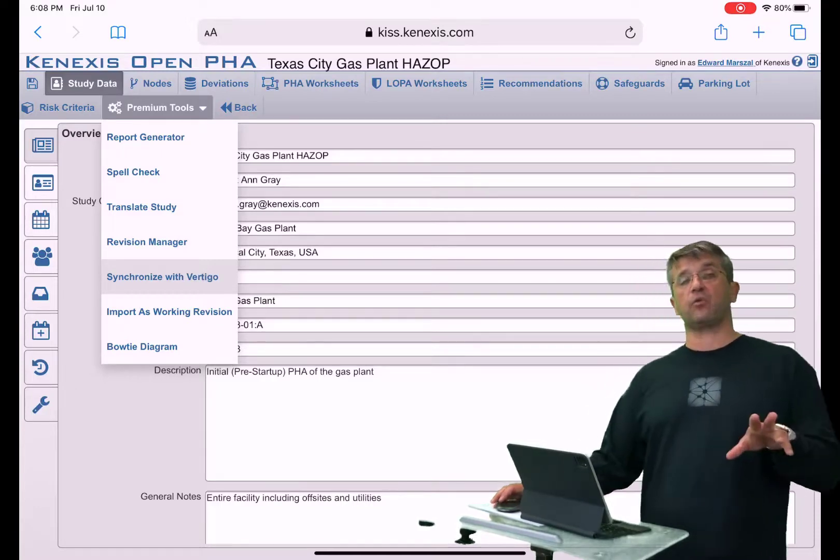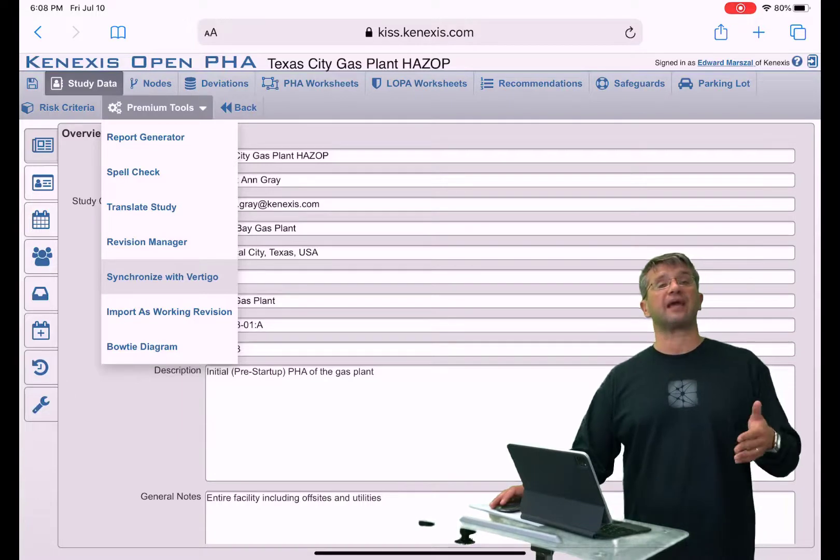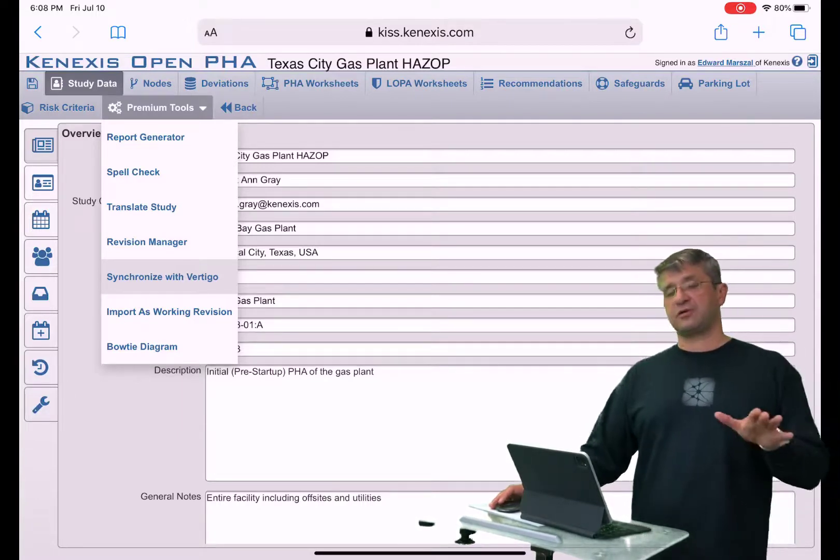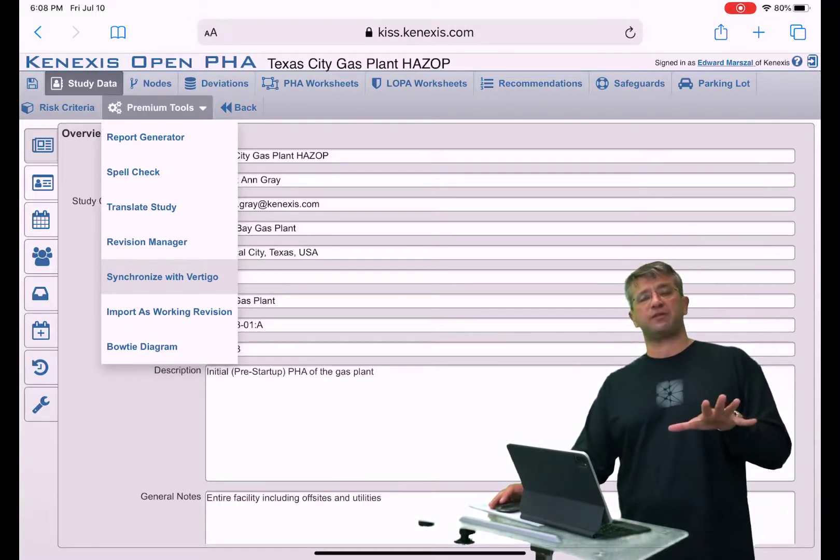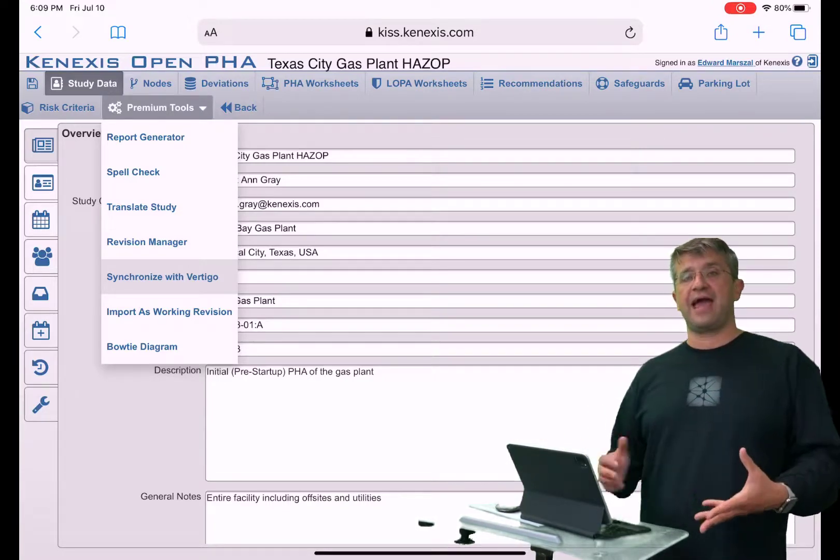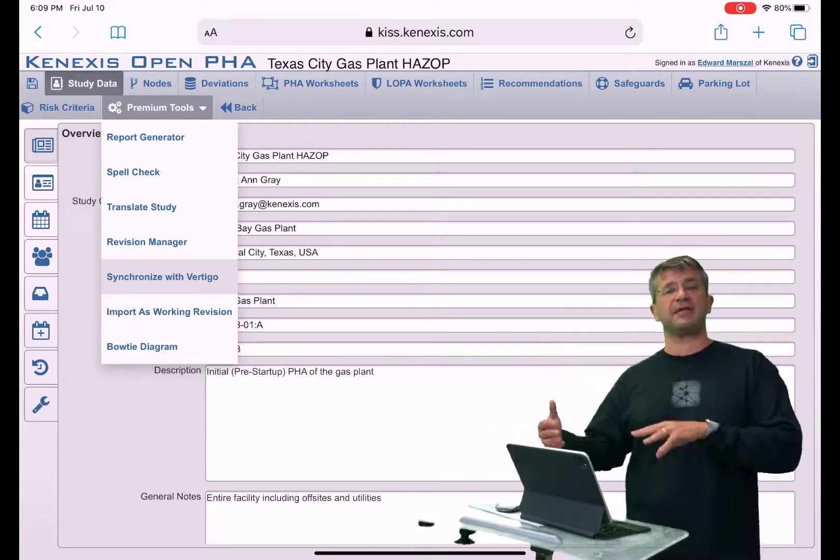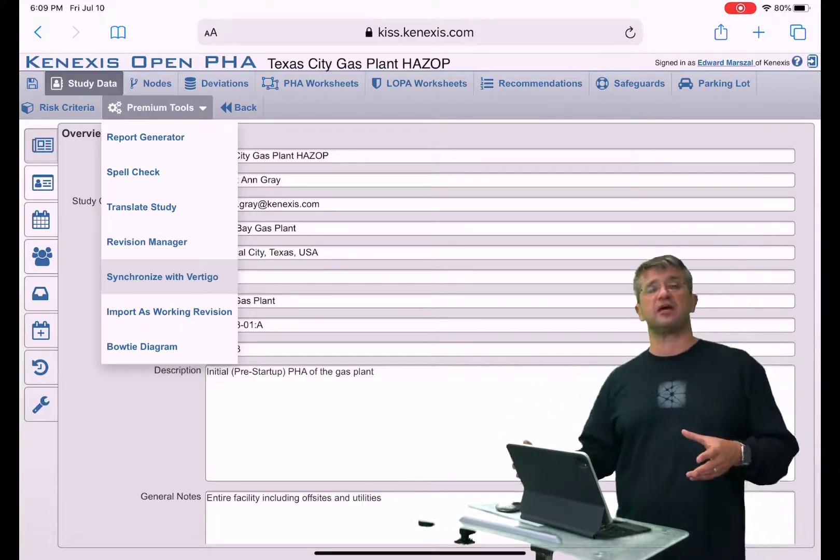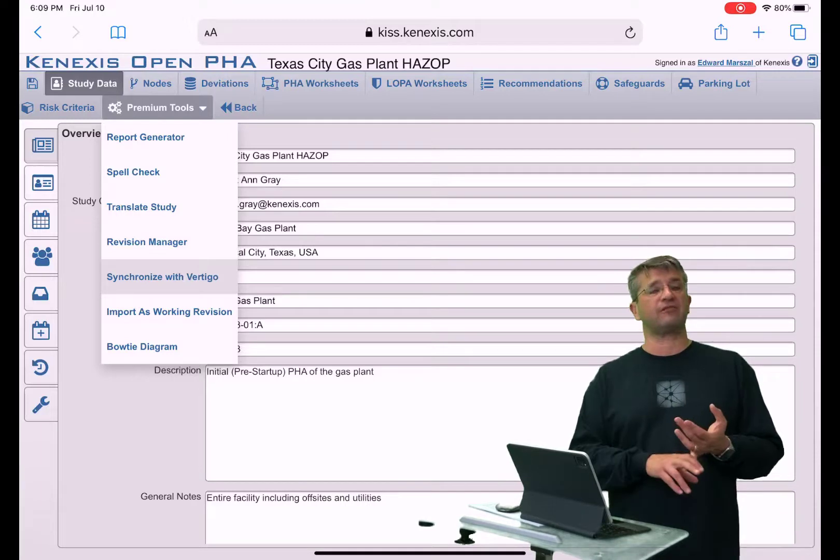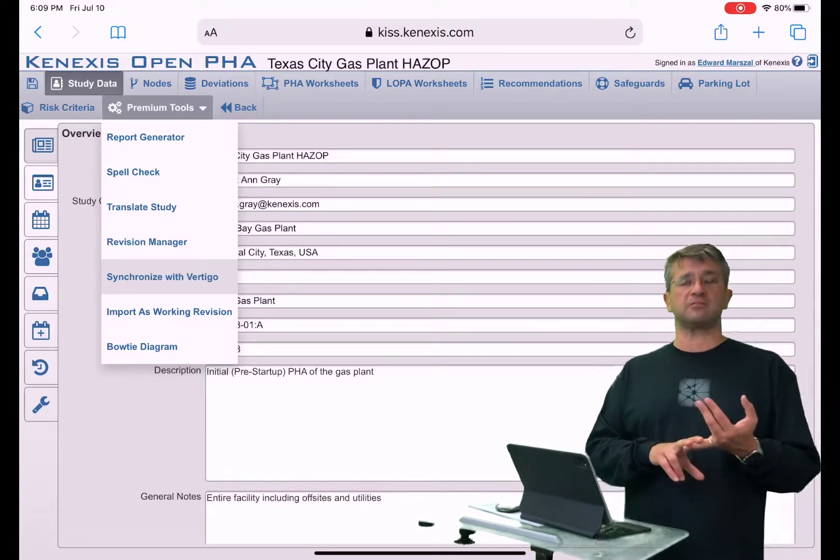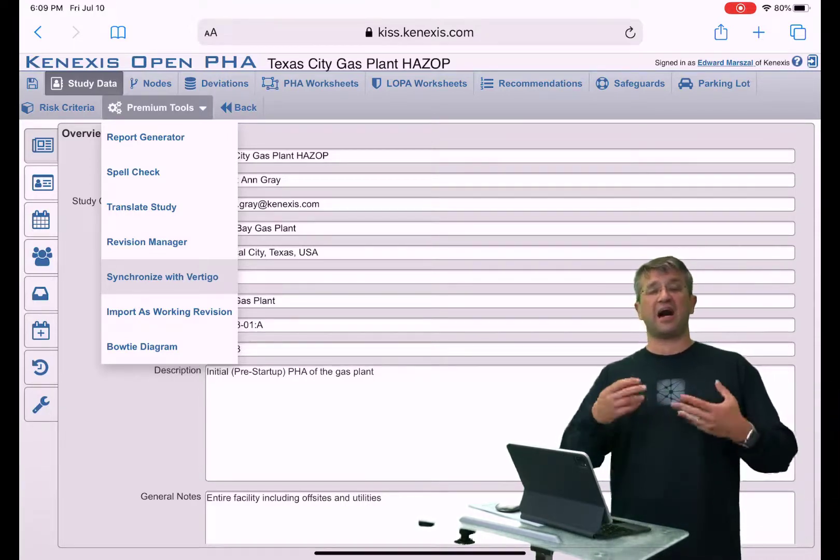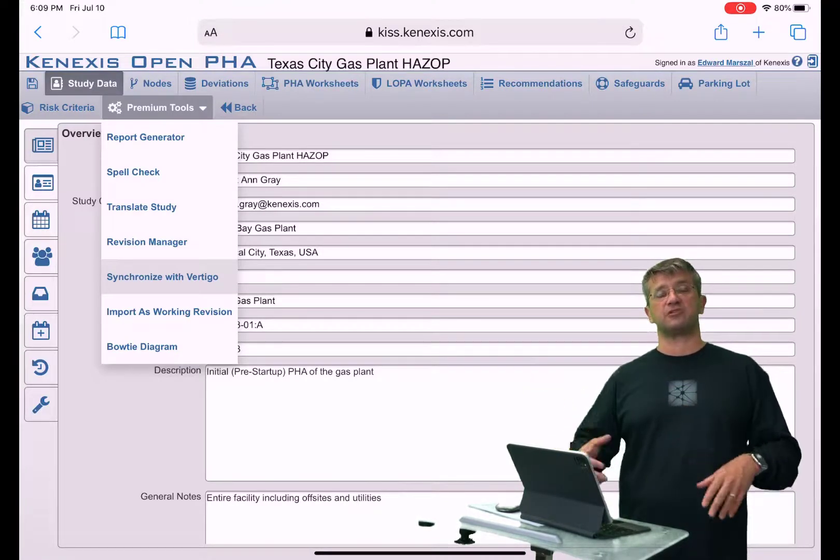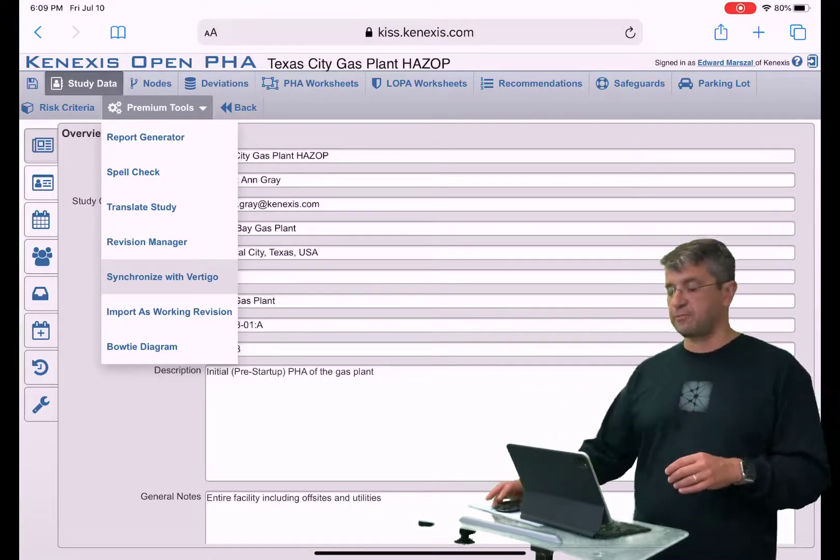Primarily when you're working with Vertigo, you're usually looking at safety instrumented functions. You could take all of the safety instrumented functions that you defined in a study and export them out to begin the workflow for designing those functions, including things like SIL verification calculations, safety requirement specifications, and then the ongoing testing of those devices throughout their entire life cycle.